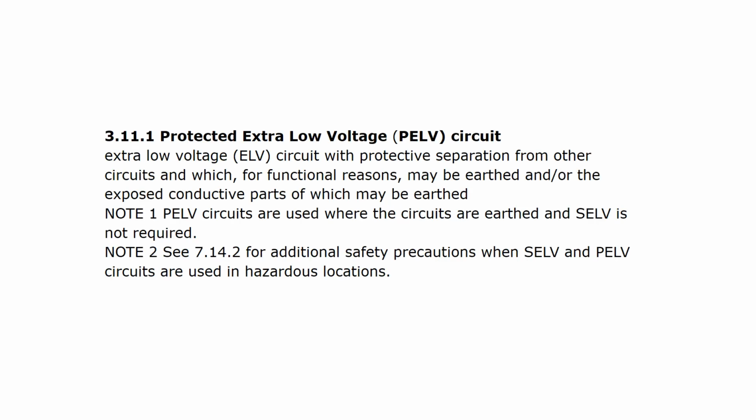Circuit. Protected extra low voltage, PELV circuit: extra low voltage, ELV circuit with protective separation from other circuits and which, for functional reasons, may be earthed and/or the exposed conductive parts of which may be earthed. Note 1: PELV circuits are used where the circuits are earthed and SELV is not required. Note 2: see 7.14.2 for additional safety precautions when SELV and PELV circuits are used in hazardous locations.